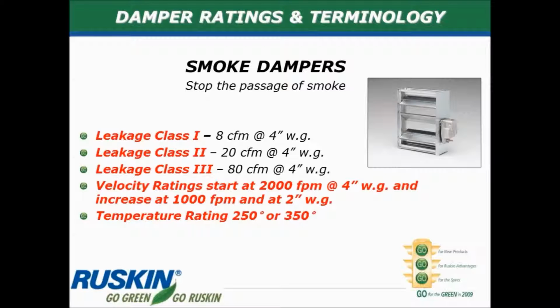The dampers also are rated for air velocity, and the minimum rating is 2,000 feet per minute at 4 inches of pressure. You can get higher ratings than that if necessary. And the temperature rating for the smoke dampers are either 250 degrees or 350 degrees.